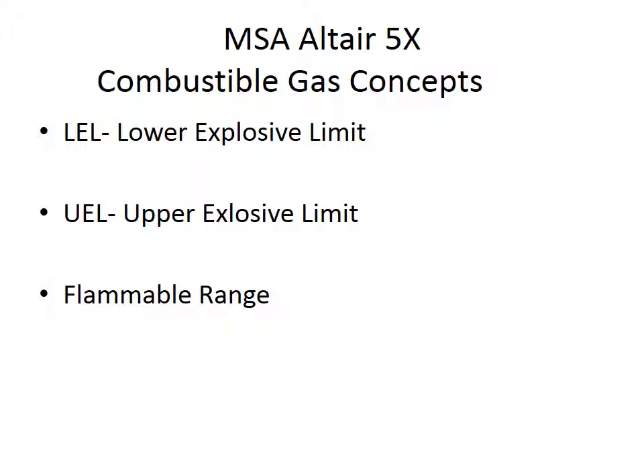The upper explosive limit, the UEL, is the highest percentage by volume of air of a combustible gas at which you can have an explosion. Everything between the LEL and the UEL is called the flammable range, kind of the danger zone. If you're below the LEL, you're in an environment that is too lean to burn, so you're not in that explosive range yet. And if you're above the UEL, you're in an environment that is too rich to burn.